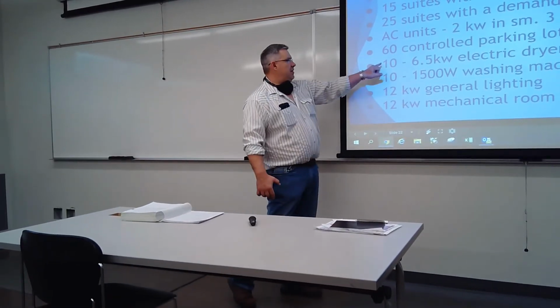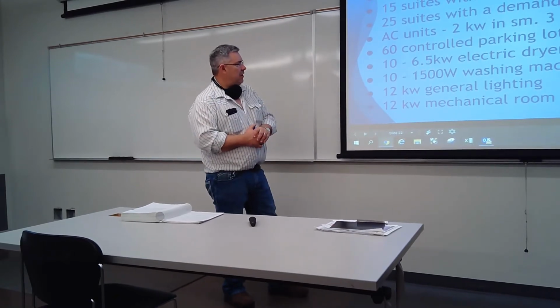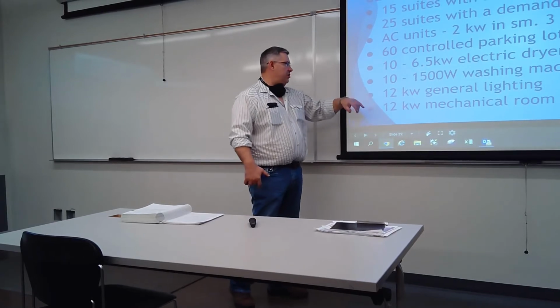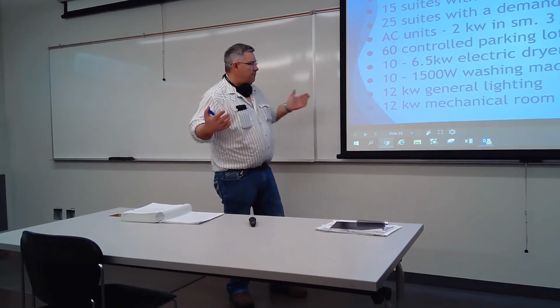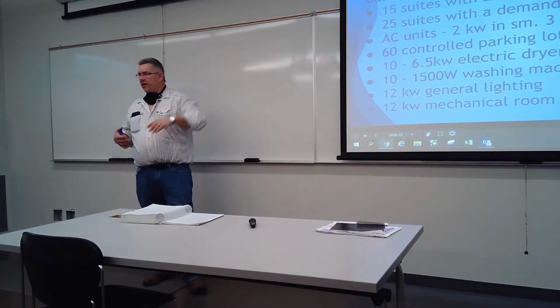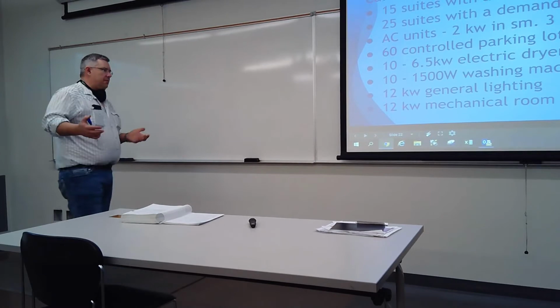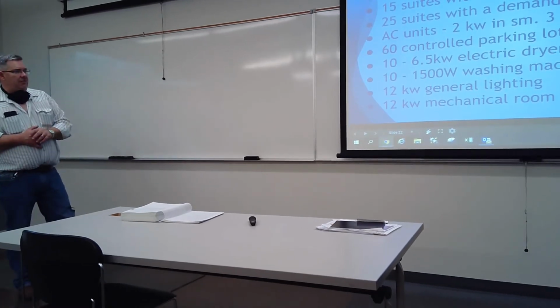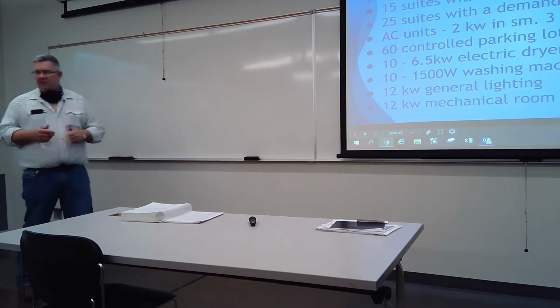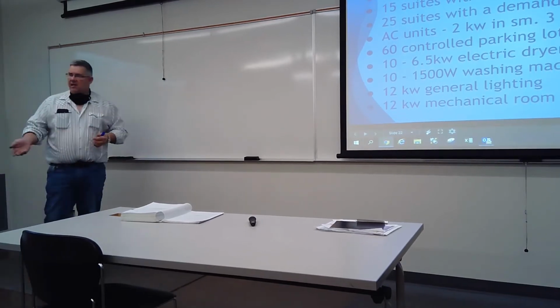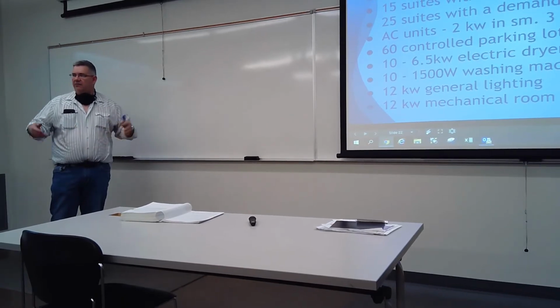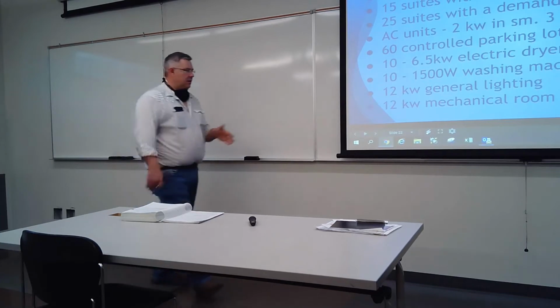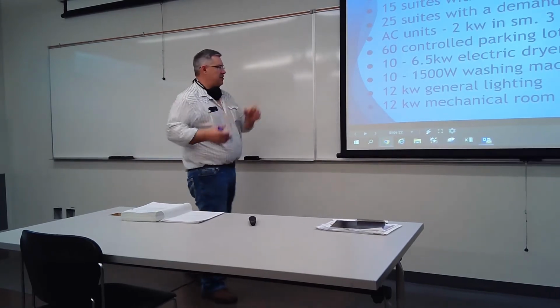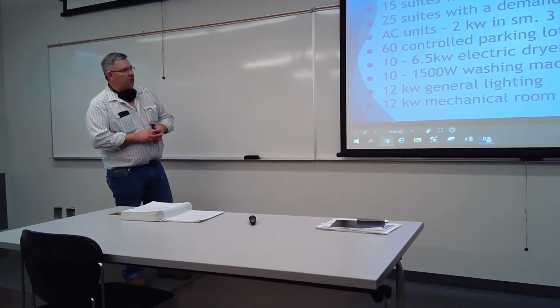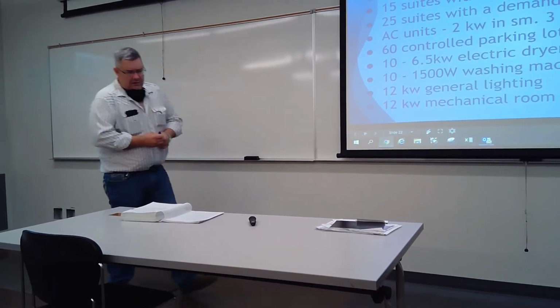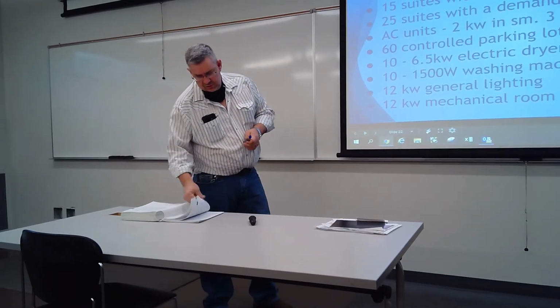and in a separate laundry or community laundry facility, or maybe there's 2 of them, we have 10 electric dryers that are each rated 6.5 kilowatts, and 10 washing machines at 1,500 watts. The lighting for the area, so the apartment lighting, parking lot lighting, outside building lighting, etc., totals 12 kilowatts. And then within the mechanical room, there's 12 kilowatts of load, right? And I didn't break it down. That could be things like heat pumps, big air handling fans, whatever the case may be. I just broke it down as all that kind of stuff that's shared by everybody. There's 12 kilowatts of it. So we're going to go to Rule 8-202.